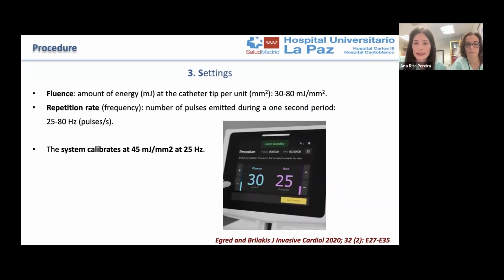Regarding the settings, there are two parameters, fluence and repetition rate, that can be adjusted and determine the total energy applied. The higher the fluence and the higher the repetition rate, the higher the energy that is applied. The fluence is defined as the amount of energy at the catheter tip per square millimeter, and usually ranges between 30 and 80.